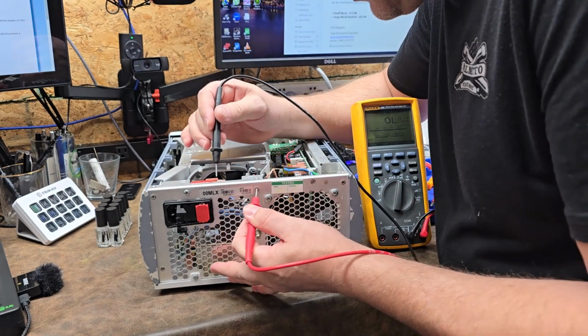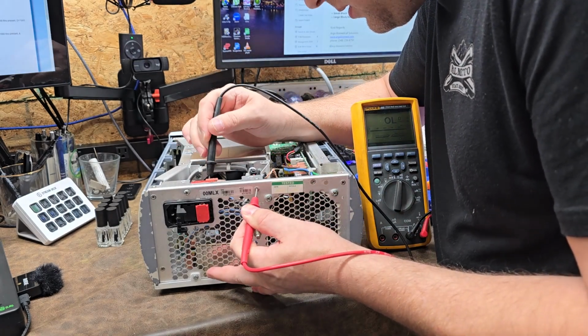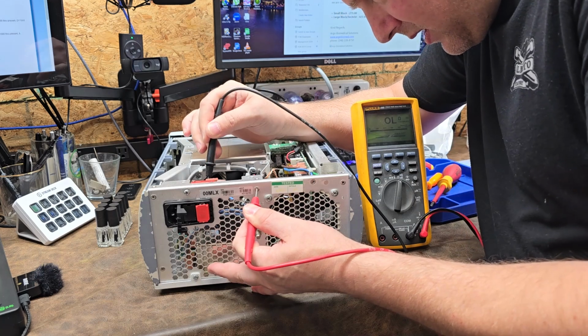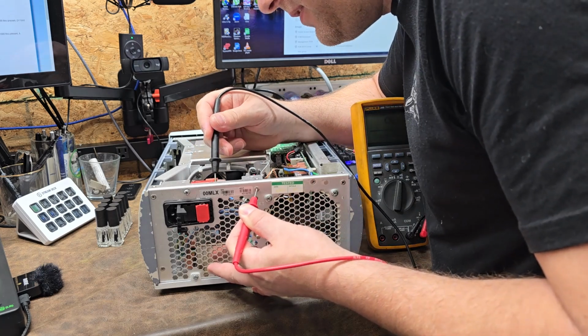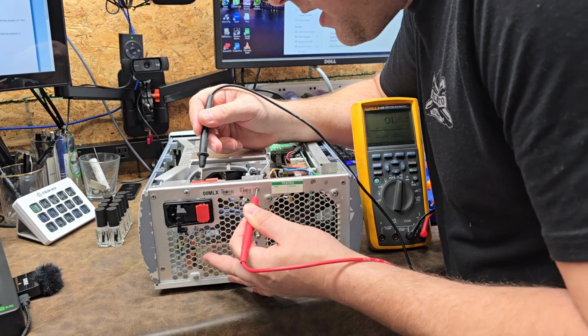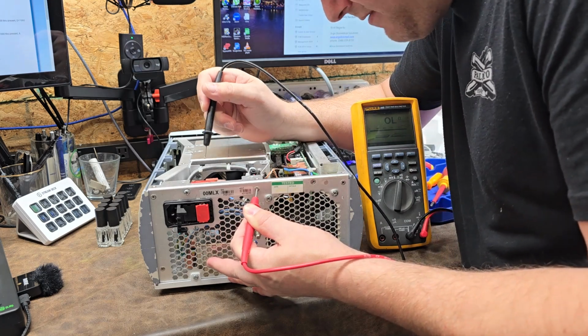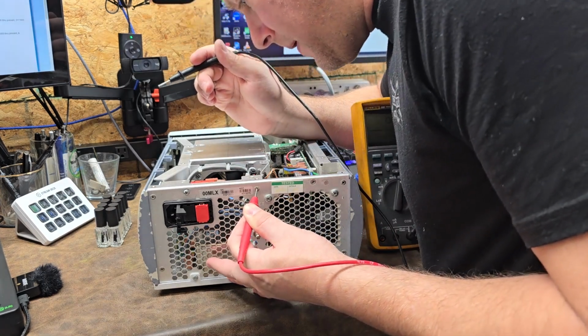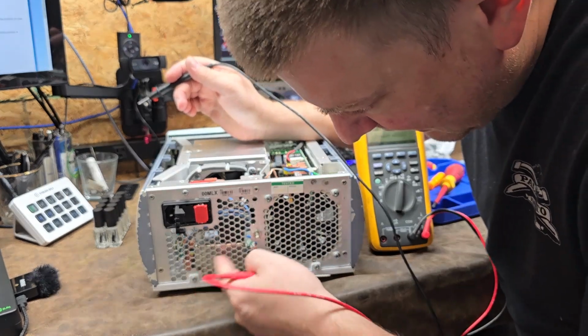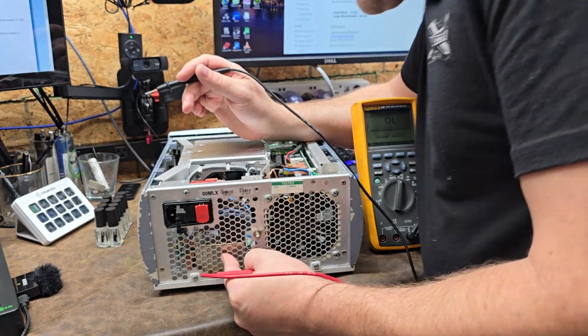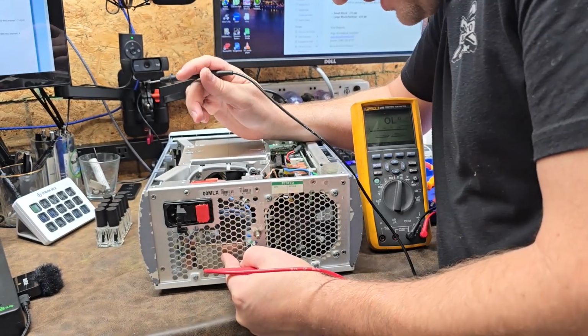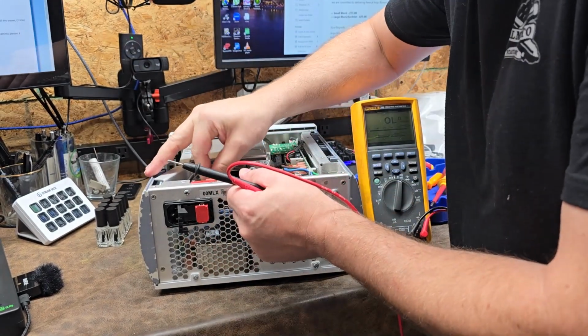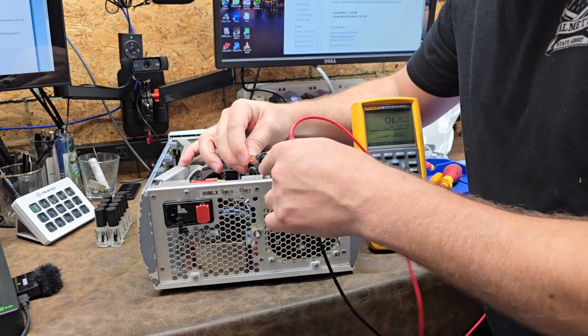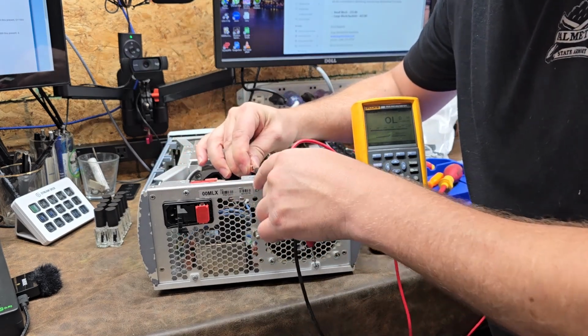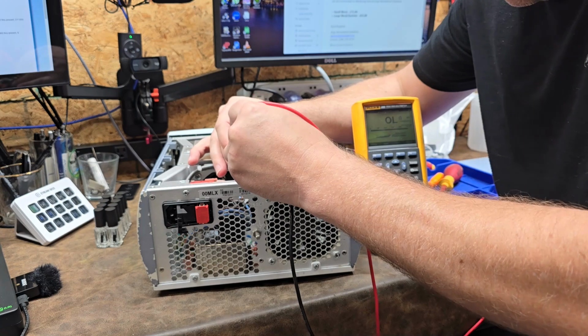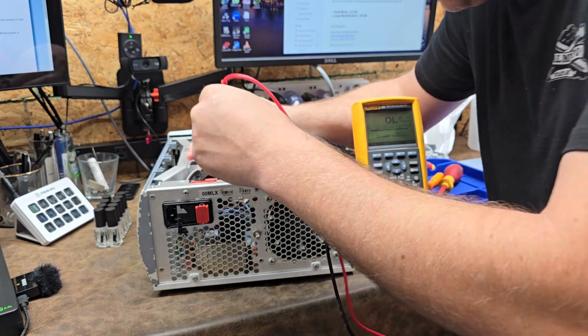Let's try from ground. So what I'm doing is I'm probing the different line options to see if I have a dead short. Now I do have an AC filter down here, and it's possible that I'm shorted at that AC filter. So I'm going to disconnect the hot and the neutral. It's showing completely open.